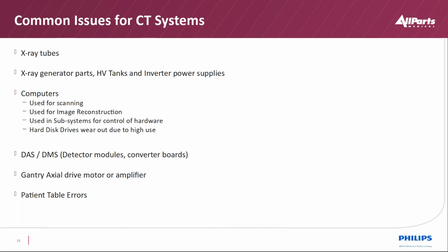So common issues, like we talked about with CT: X-ray tubes are the biggest cost with regards to service. In some systems, the X-ray tube is 184,000, 190,000. Some of the higher end systems are out there even higher. There are systems that have 2 X-ray tubes. In the case of Siemens, they have the Flash and a couple of different models where you have 2 X-ray generators, 2 X-ray tubes, 2 detector sets, all in the same gantry. So cost to serve is quite high.